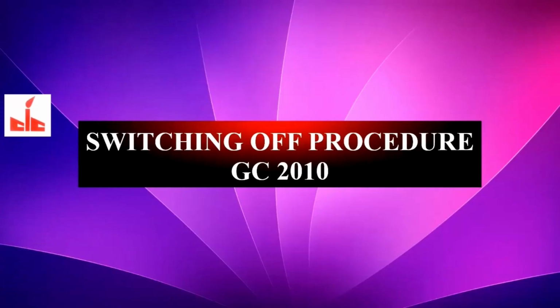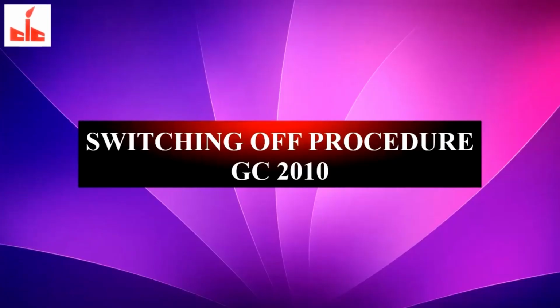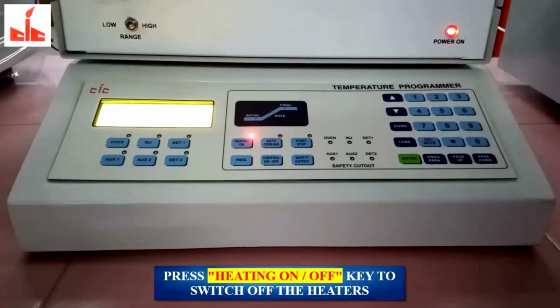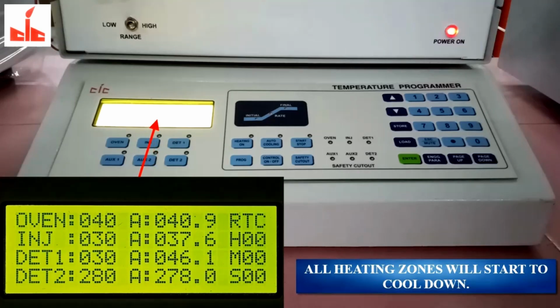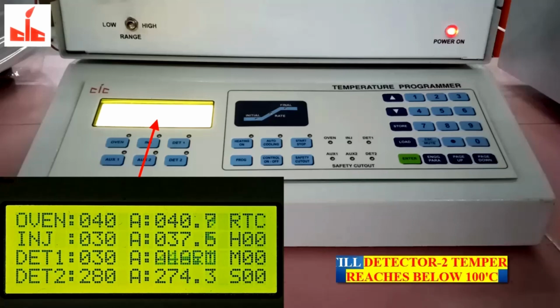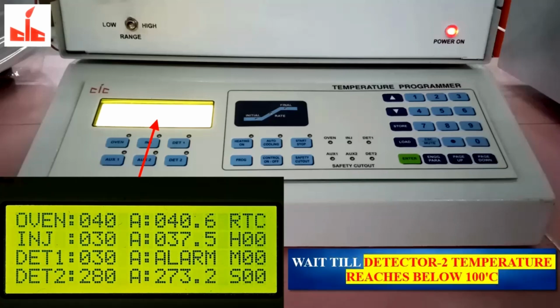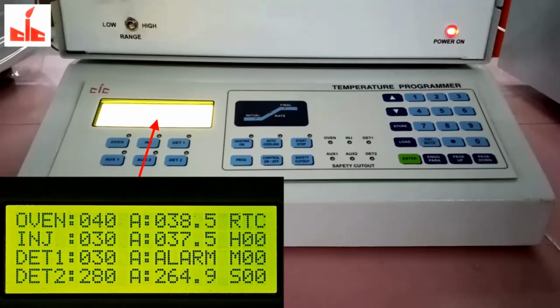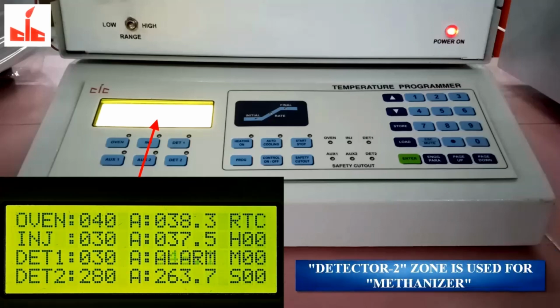Switching off procedure of GC 2010. Press the heating on and off key to switch off the heaters. All heating zones will start to cool down. Wait till the detector 2 temperature reaches below 100 degrees centigrade. Detector 2 zone is used for the methanizer.